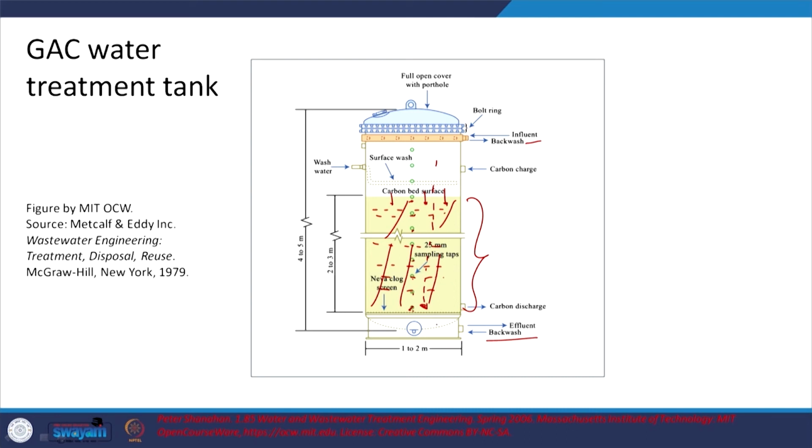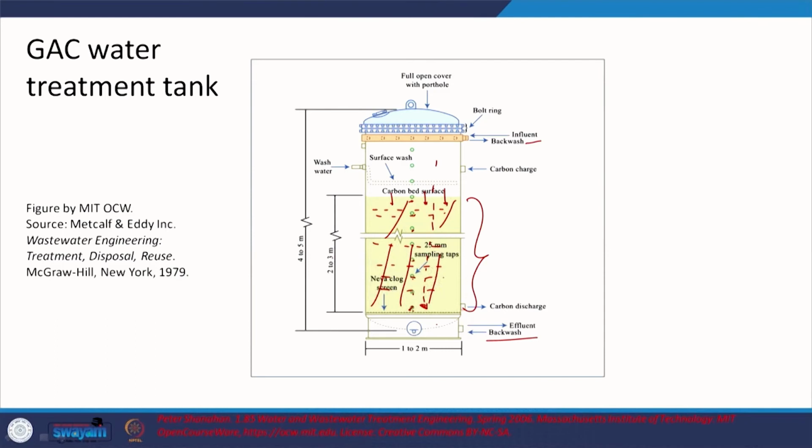Or one other way is to look at the amount of pressure or head, that is head loss that is occurring. That will also give you an idea about when you need to backwash or if it is already exhausted. Typically, we look at head loss for looking at how frequently you need to backwash the media. So, that is what you see backwash setup to, right.